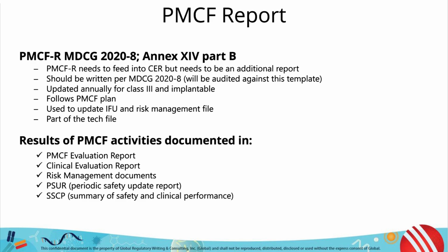PMCF data are required to be detailed in a standalone report, and MDCG 2020-8 gives us a PMCF report template that should be used or referenced. The PMCF report should follow the prepared PMCF plan and in turn be used to update the IFU and risk management report and feed into the CER, PSUR, and SSCP. In your PMCF report, be sure to include a justified time schedule for updates based on rationale related to the expected device lifetime.